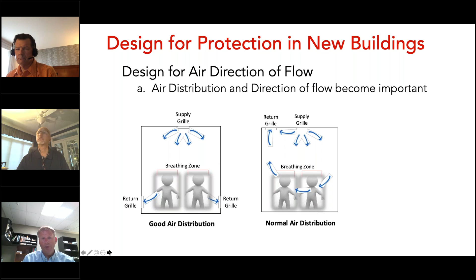What we like to see is separating those two: put the supplies at the top, put the return grills closer to the floor, and pull that air across the breathing zone instead of returning it back across. You can't do that in every building, but that's really the goal, to provide airflow distribution across the entire zone.